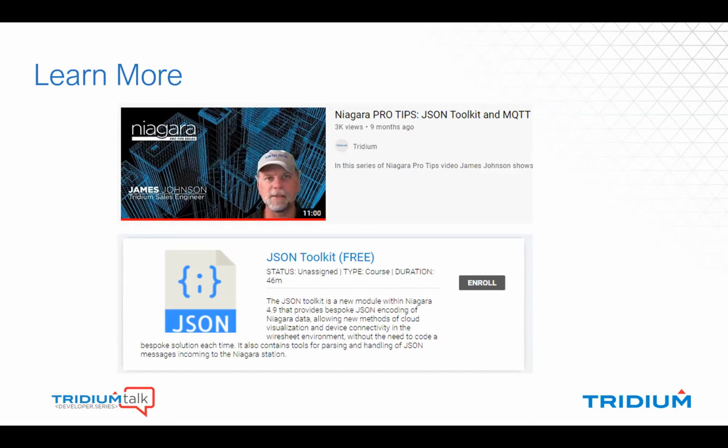Next question. Can I turn the whole station into a generic schema and then use that HTTP access provided as a REST API for all of Niagara? Yes, you can certainly link the JSON schema up to a HTTP transport if that's what you would like to do. In terms of turning the whole station into a generic schema, I think that's where the relative schema that we touched on towards the beginning of the presentation comes into play, in that you can have a message format that contains just that point's worth of data, and you could subscribe to many points.